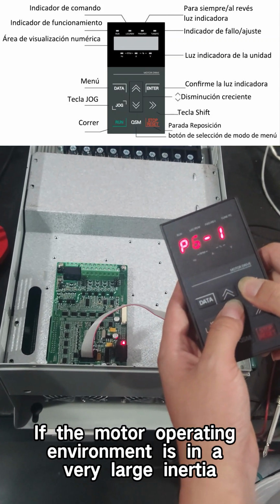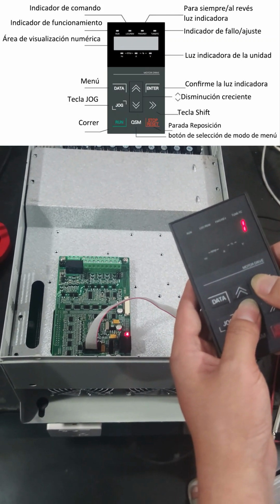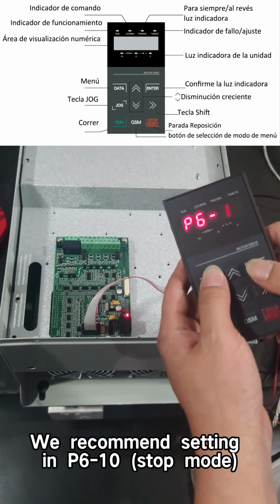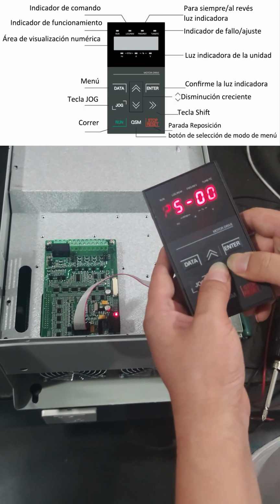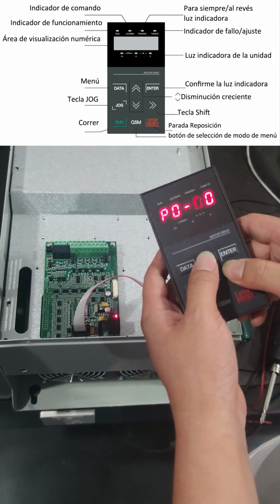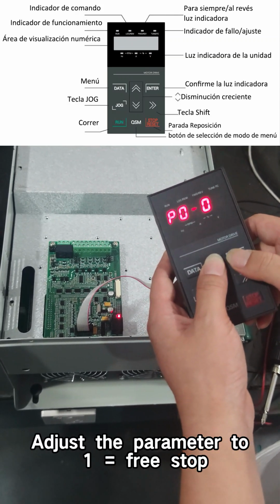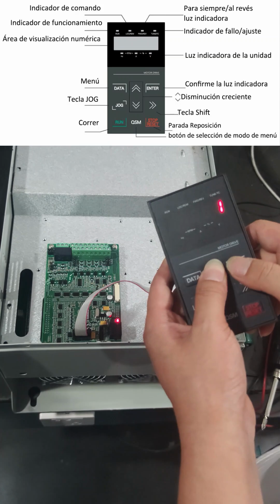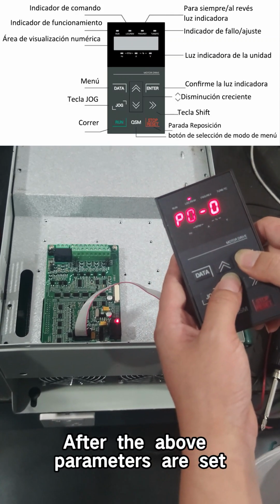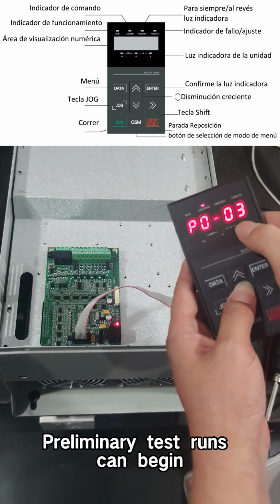If the motor operating environment has a very large inertia, we recommend setting P6-10, stop mode. Set the stop method to free stop. Adjust the parameter to 1 equals free stop. After the above parameters are set, preliminary test runs can begin.